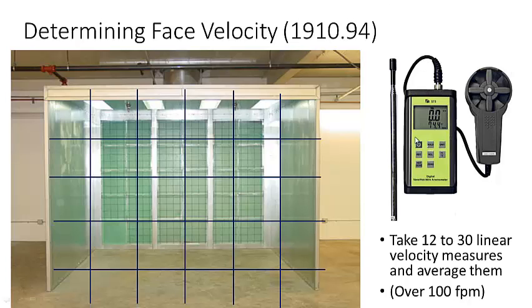To measure face velocity, you use an anemometer — a linear air speed instrument. The one on the left is a hot wire anemometer; the one on the right is a propeller type. You hold it away from your body and create a pseudo grid across the face of the booth. You can take 12 to 30 measurements across a grid — for example, a three-by-four or five-by-six pattern — and average the results. According to the standard, depending on booth size, the minimum is either 100 feet per minute or 150 feet per minute.